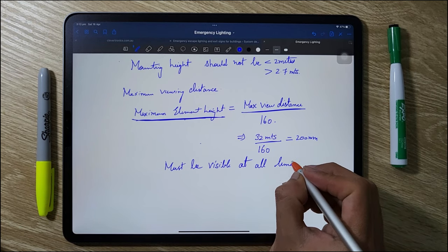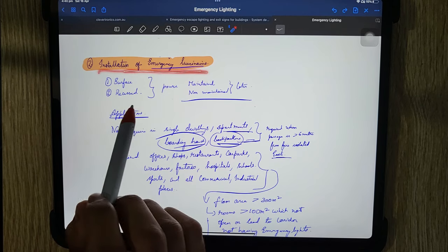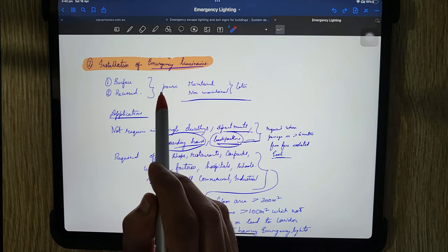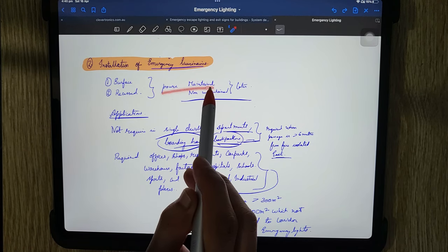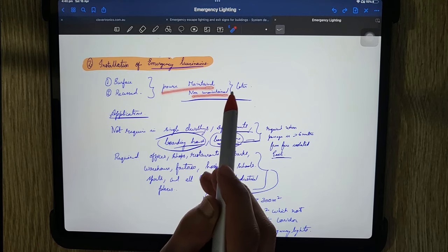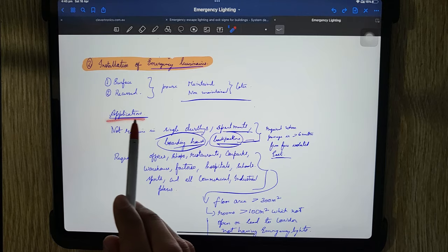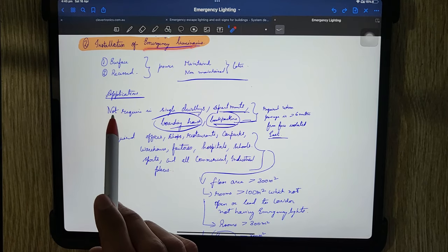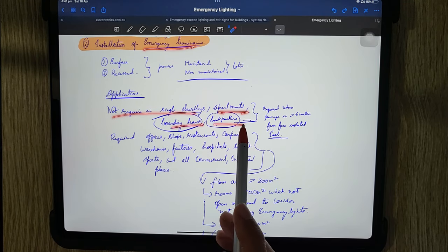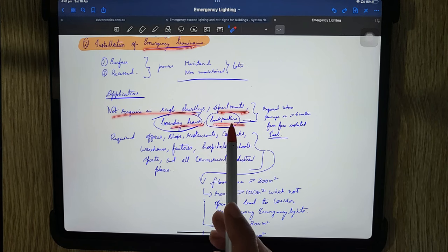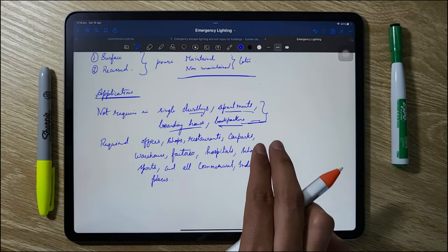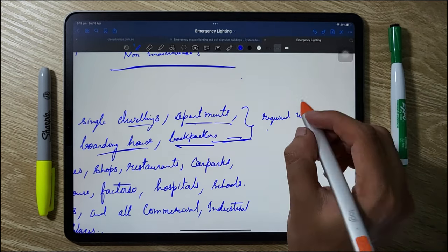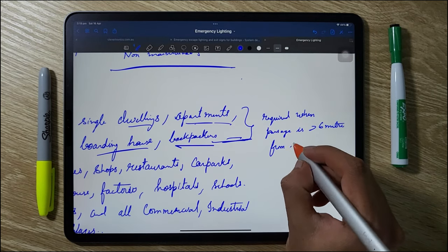Now let's jump to the second part: the designing of emergency escape luminaires. Emergency escape luminaires are of two types — surface mounted and recessed — and they are either maintained or non-maintained, which will be discussed later. Emergency lighting is not required in a single dwelling house, apartment, boarding house, or backpackers house if the distance of travel from the door of the unit is not greater than 6 meters to a fire-isolated exit. However, if the distance is greater than 6 meters, emergency lighting is required in any passageway, corridor, or hallway.